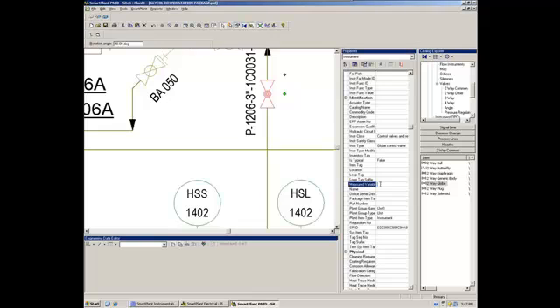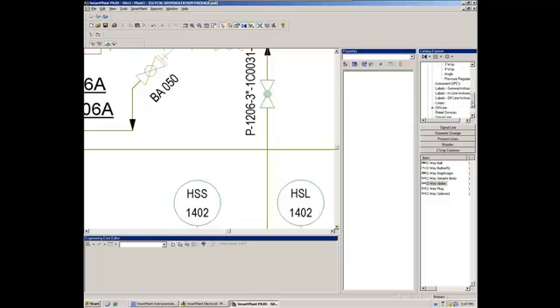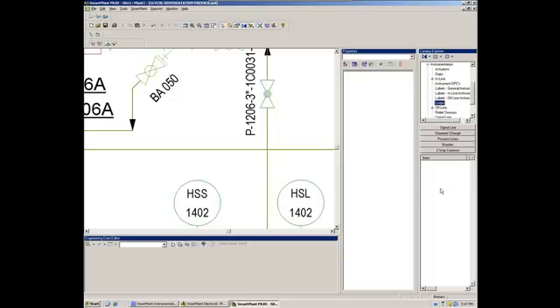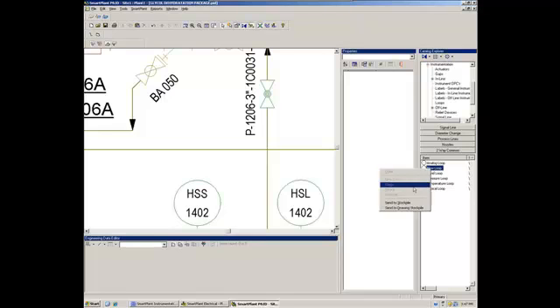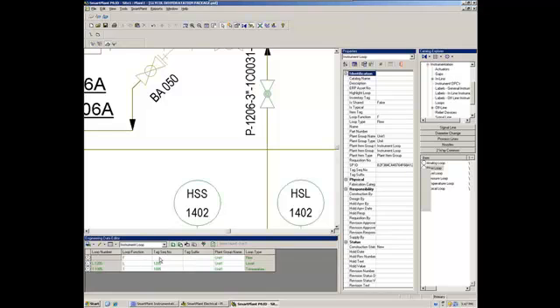So the measured variable will be, and actually, first of all, I will create a new loop because I want to retrieve this loop in SmartPlant instrumentation, so in SmartPlant P&ID, and we will see that later during the standalone demo, we can store in a stockpile the loops. Okay, so what I will do is to create a flow loop. Let me just create a flow loop here, instrument loop. I have my new loop here, and I will call it F1040, for example.